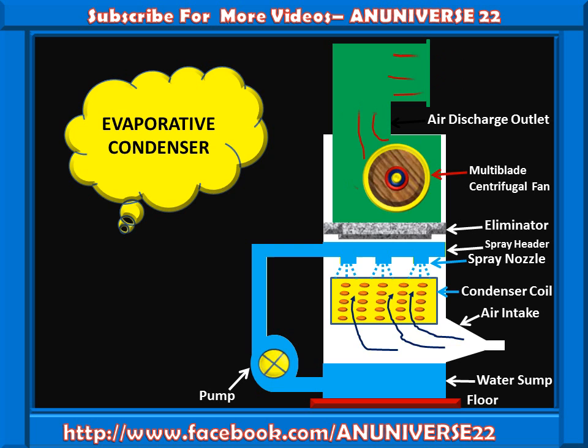Here, eliminator is provided above the spray header to stop the particles of water from escaping along with the discharged air. The spray water coming in contact with condenser tube surface evaporates into the airstream. The source of heat for vaporizing the water is taken from refrigerant, thereby cooling and condensing the gas.